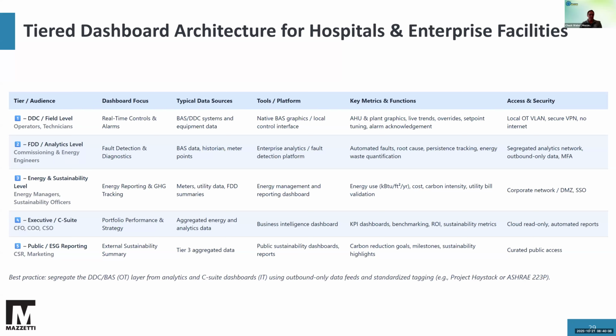Now, when you have a drift or a problem in level 3, you're going to have to go to level 2 and figure out where your problem lies, then go to level 1 to dive deeper into where that problem exists. So when you're integrating these, I recommend you start with level 1. Get your DDC correct, get your point naming correct, use point naming conventions like Project Haystack, and there's also an ASHRAE guideline for point naming convention.